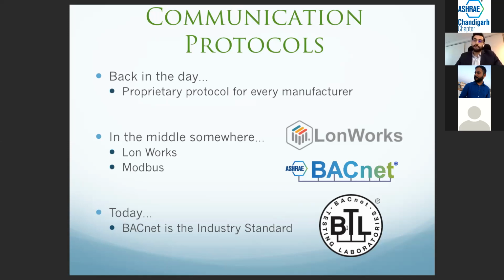If there are any consulting engineers here, this is typically a stamp, BTL, a third party to which every manufacturer sends their products, and they do all the testing. They check for interoperability to see if manufacturer A's product works well with manufacturers B, C, D, and they give them the okay. On the BTL website, you can see all the manufacturers listed, all their products listed, and which products are approved by BTL. Consulting engineers use phrasing in their specifications such as the product supplied by the controls contractor will be BTL tested. So if you're a consulting engineer, this is something you may want to look into.